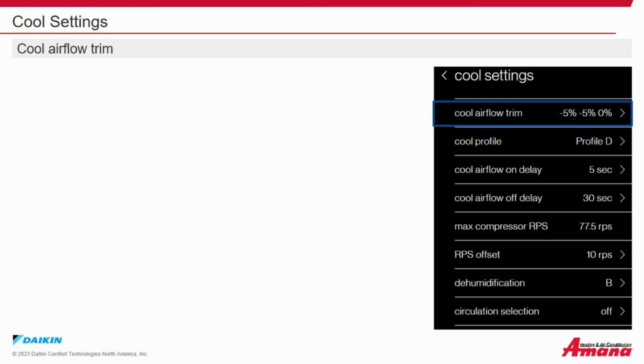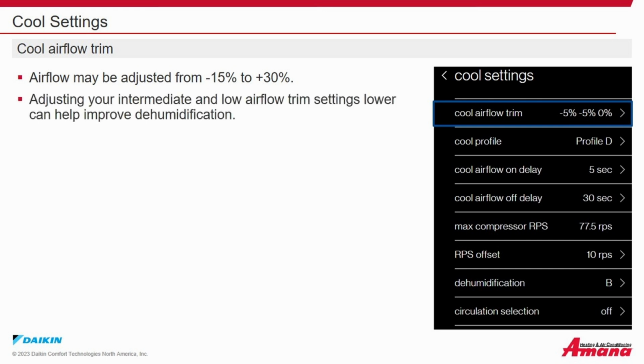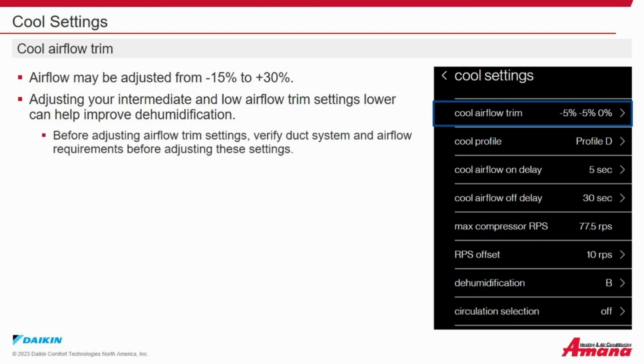Cool settings. Cool airflow trim. Airflow may be adjusted from -15% to +30%. Adjusting your intermediate and low airflow trim settings lower can improve dehumidification. If you're planning to adjust the airflow trim settings, verify duct system and airflow requirements before adjusting these settings. Refer to the Installation Operation Manual for restricted airflow combinations.